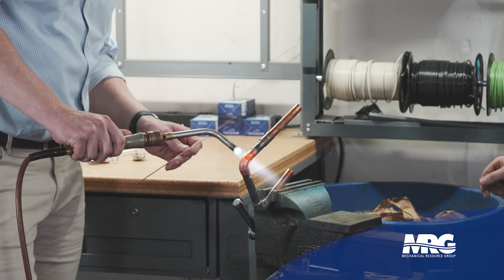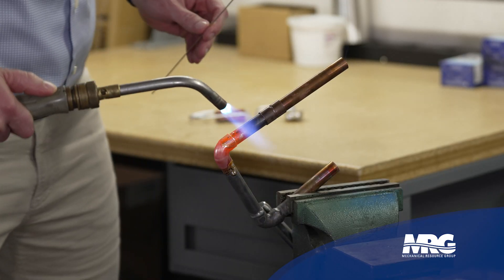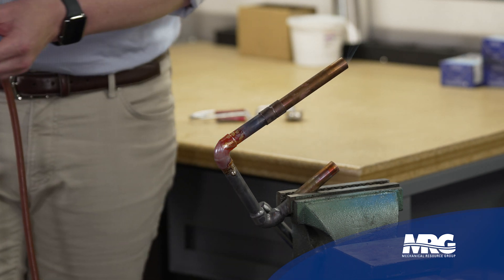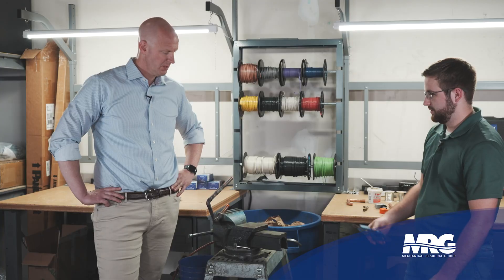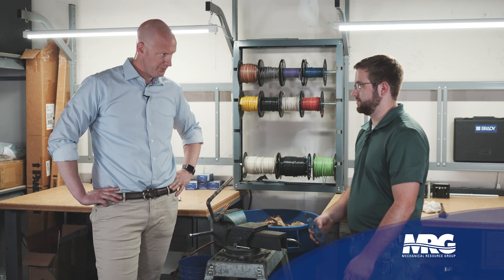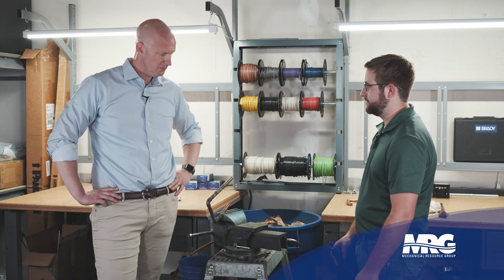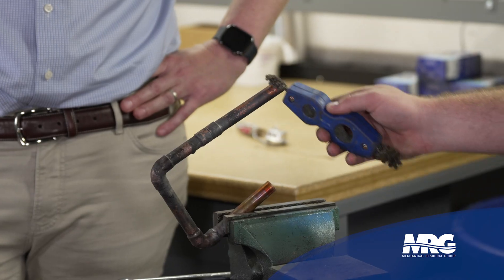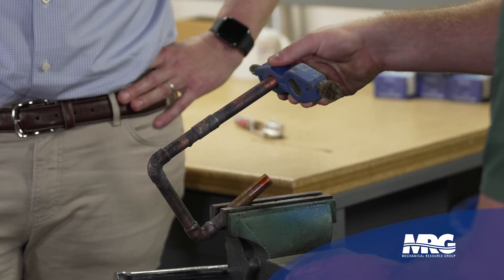All right, we're going to do this joint right here. Remember you want to hold your heat on the backside of that joint. You want to put your heat where you want your Sil-Fos to go. Get the bottom side a little bit more. Got a little hot. So now that it's cooled down some, we're going to go ahead and prepare it to soft solder. We want to clean off this carbon buildup that we made. So we'll take a pipe cleaner right here.